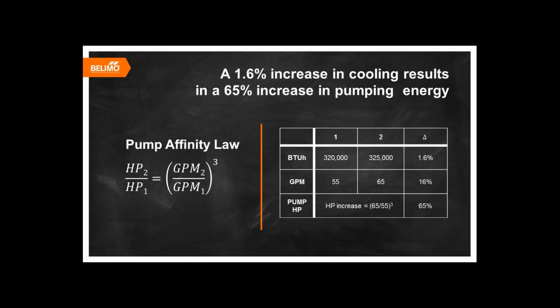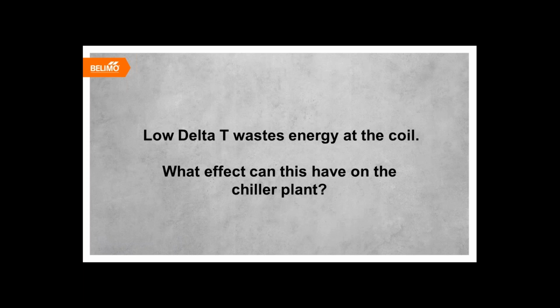What this proves is that operating in the waste zone can be very costly, as we're using extremely high pumping energy to produce very minimal additional heat transfer. We see that low delta T wastes energy at the coil, but what effect can this have on the chiller plant?